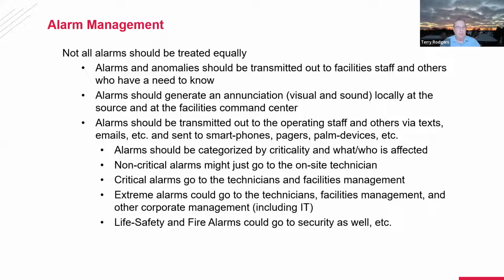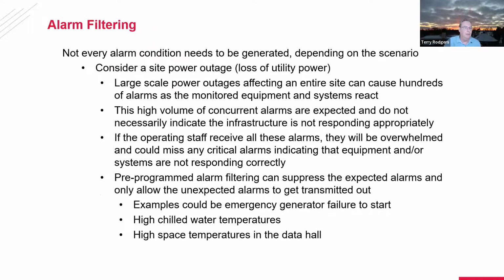And then the alarms should be categorized by criticality, and those criticalities should also define who gets notified of various issues. Non-critical alarms might just go to your on-site technician, so he knows there's a problem and goes and fixes it. Critical alarms could go not only to the technicians, but to facilities management, alerting them that there's a bigger issue at stake. Extreme alarms could go to the technicians, the facility management, and other corporate management. And in my case, with data centers, it could include the NOC, or the Network Operations Center, or the IT command center. And then, of course, life safety and fire alarms could go to security and other people who have specialized duties to respond to that stuff.